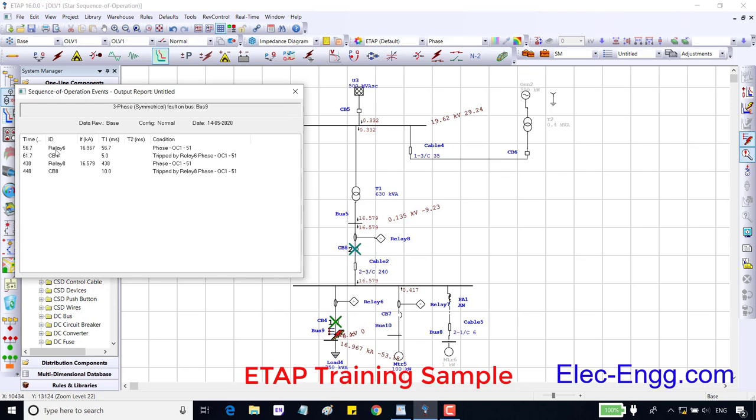Preview the timestamp, like an event viewer in the substation automation system. Here also we can see the events happening with the timestamp. With this time delay, 56.7 milliseconds, relay 6, element 50.